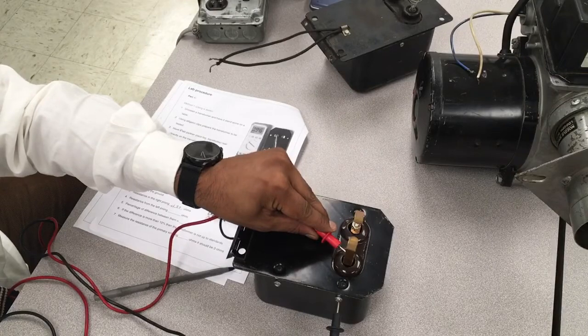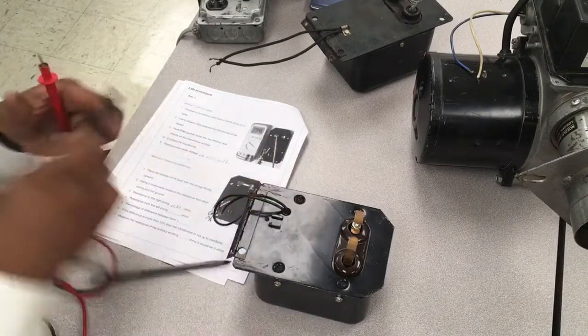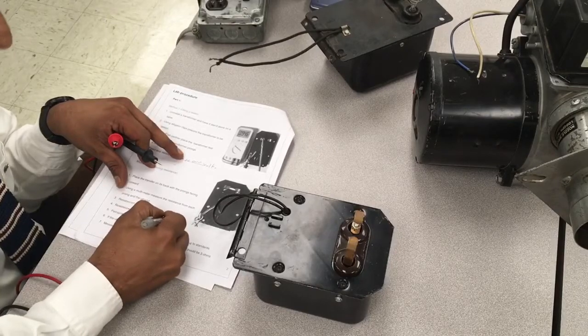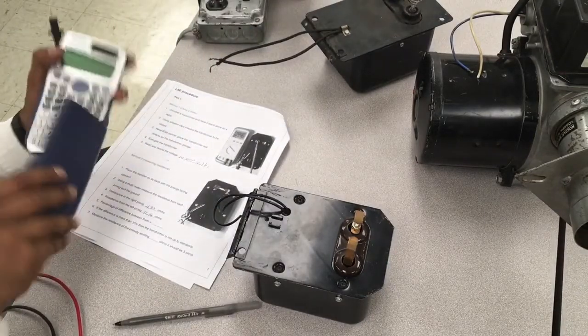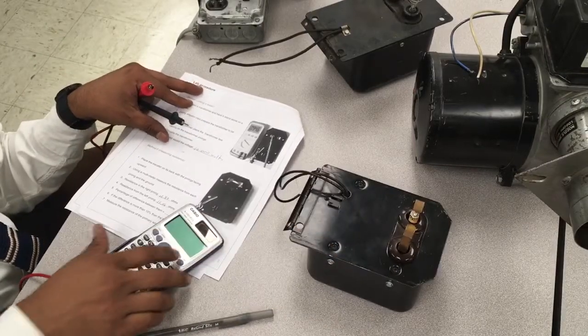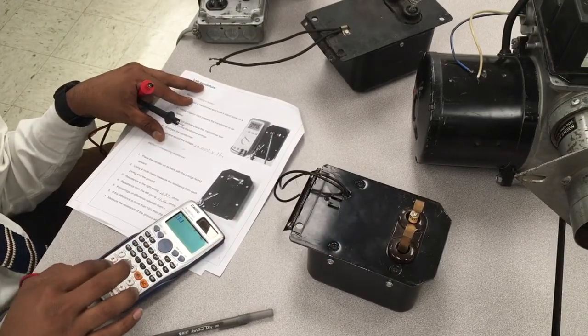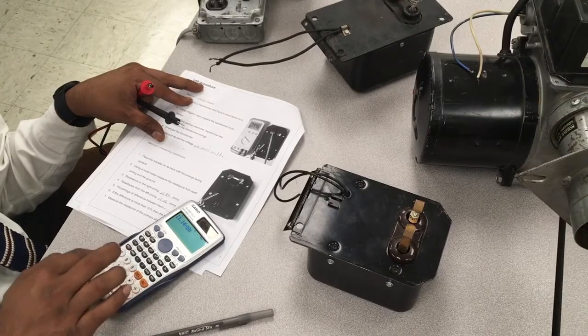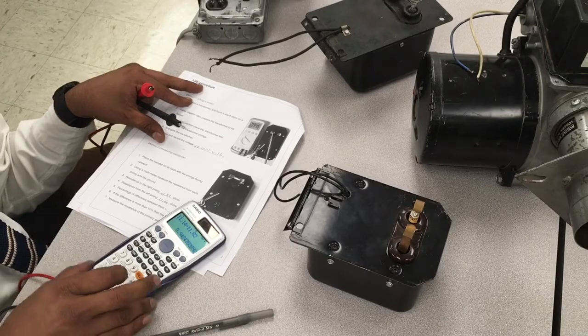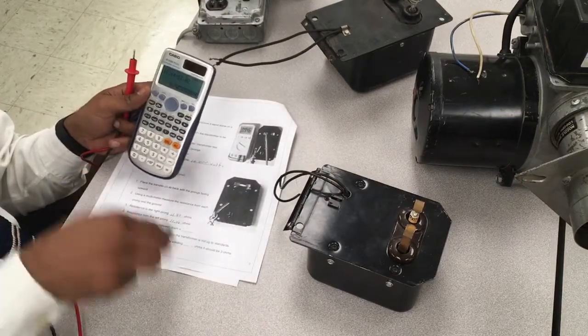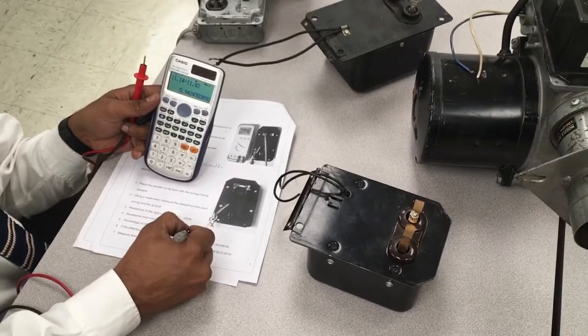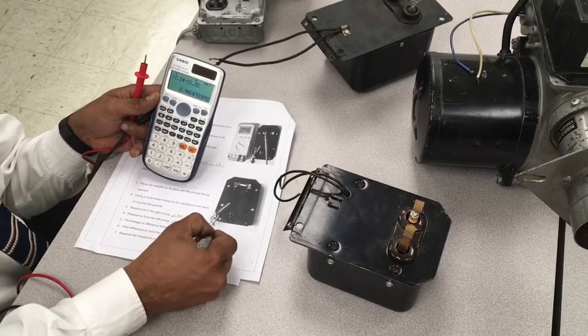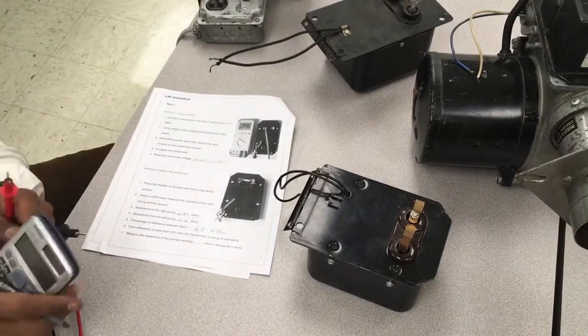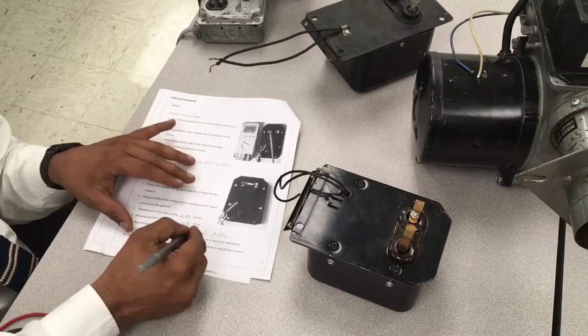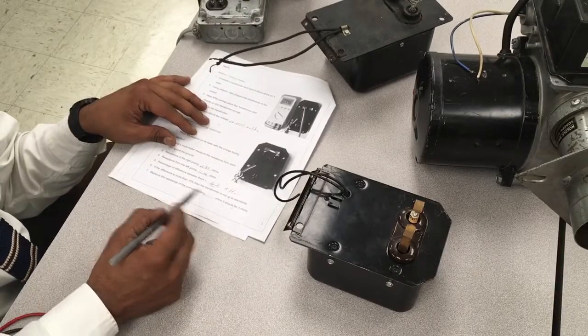I measure from the other side, 11.14, and I will use the calculator to get the percentage of these two. I divide 11.14 by 11.82, and they are about 6%. So this is 94% of the other, so they are about 6% different. Anything more than 10% is not good. 6% is okay. That means the winding is still very good.